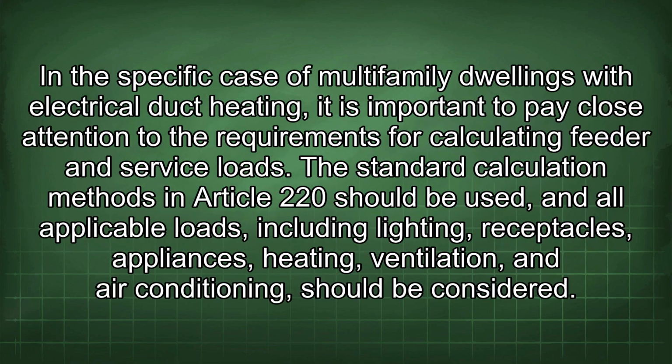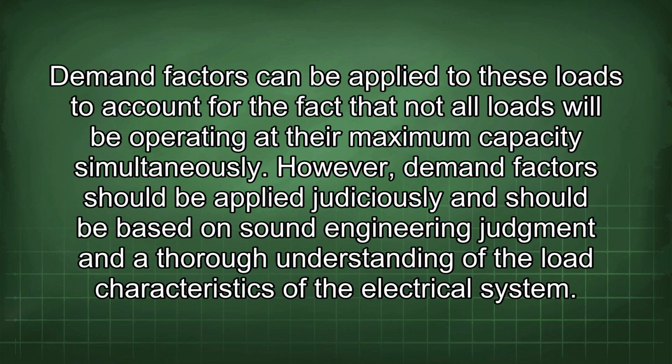In the specific case of multifamily dwellings with electrical duct heating, it is important to pay close attention to the requirements for calculating feeder and service loads. The standard calculation methods in Article 220 should be used, and all applicable loads, including lighting, receptacles, appliances, heating, ventilation, and air conditioning, should be considered. Demand factors can be applied to these loads to account for the fact that not all loads will be operating at their maximum capacity simultaneously. However, demand factors should be applied judiciously and should be based on sound engineering judgment and a thorough understanding of the load characteristics of the electrical system.